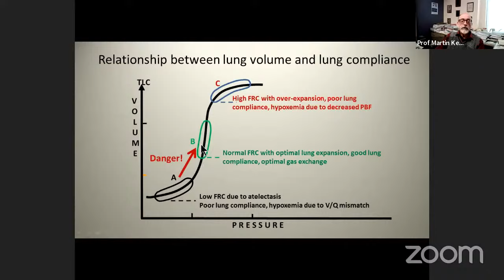So how did we come to tackle this? Many papers, publications, chapters use the term volume targeted ventilation to describe any modality that pays attention to tidal volume, conflating volume controlled ventilation and volume targeted ventilation. I make a distinction because volume controlled ventilation, as I explained to you, has certain important limitations. Volume targeted ventilation, in fact, is pressure controlled ventilation with automatic adjustment of inflation pressure to maintain a stable tidal volume. It is not the same thing.